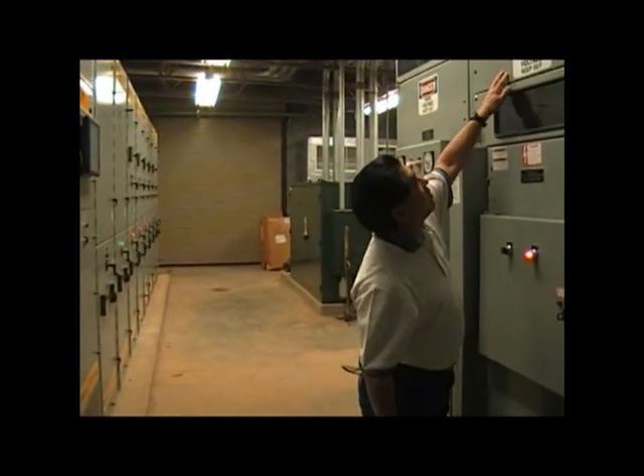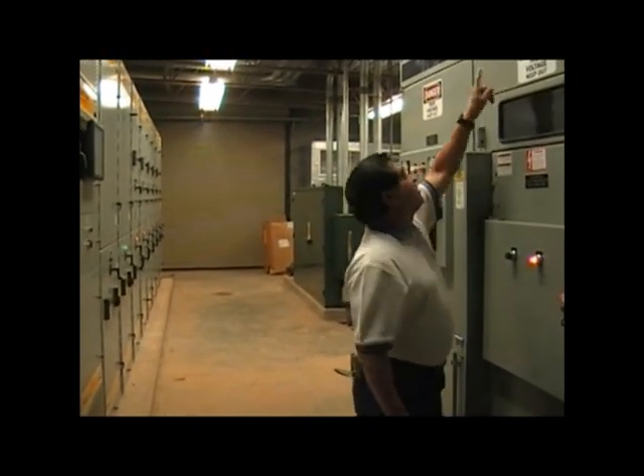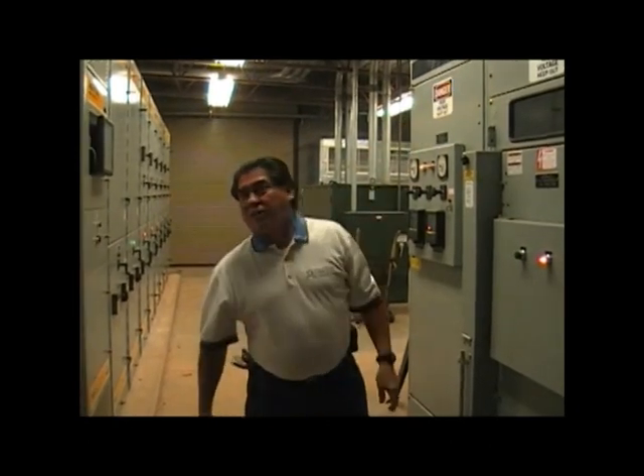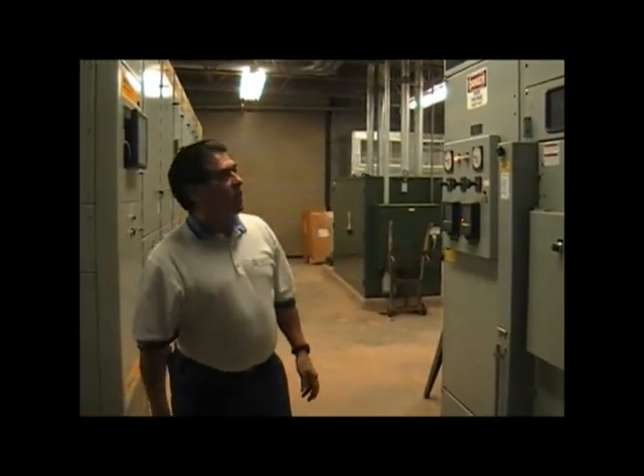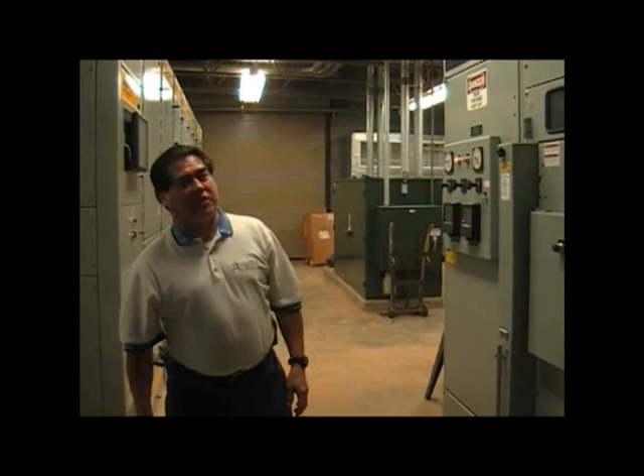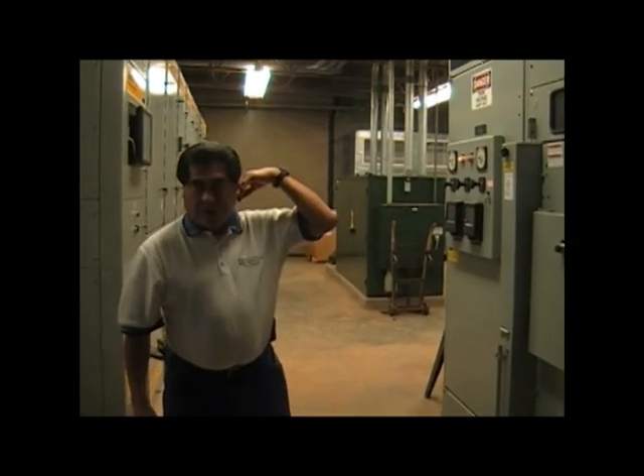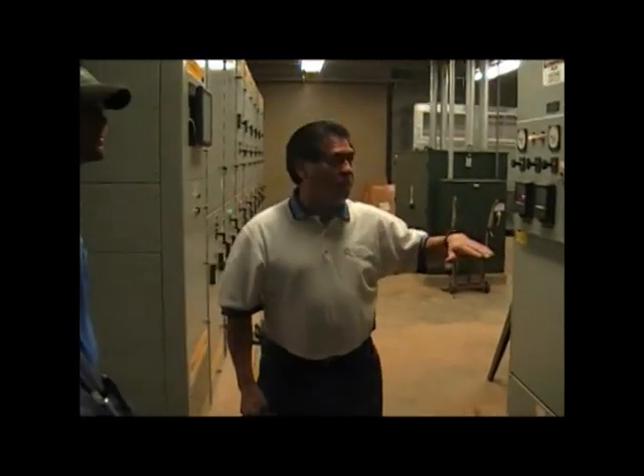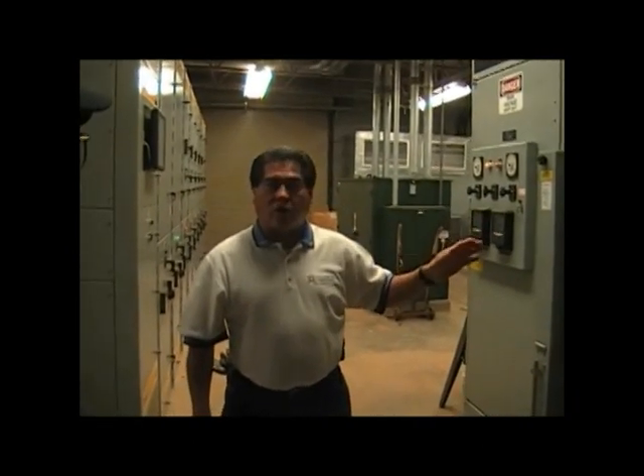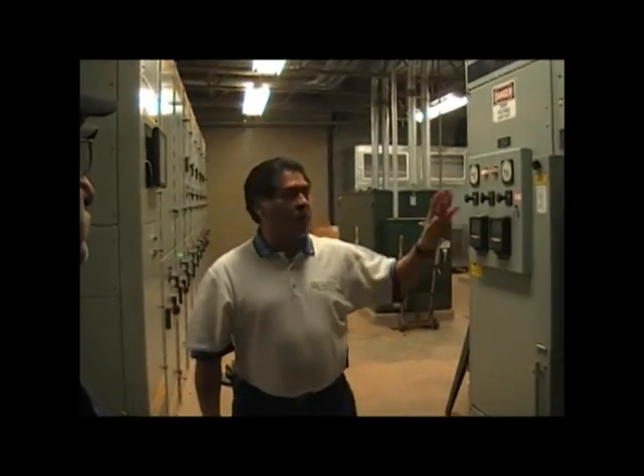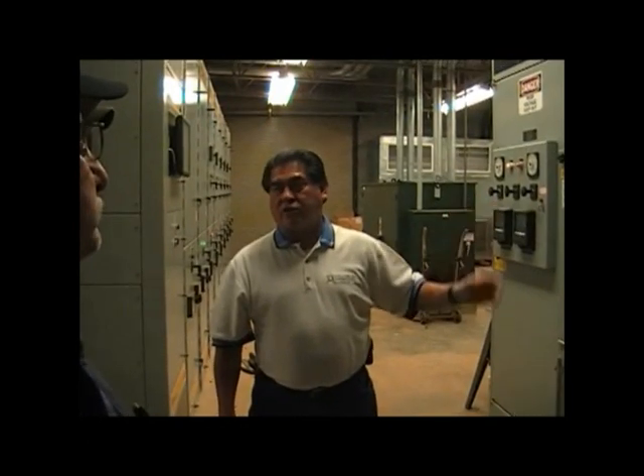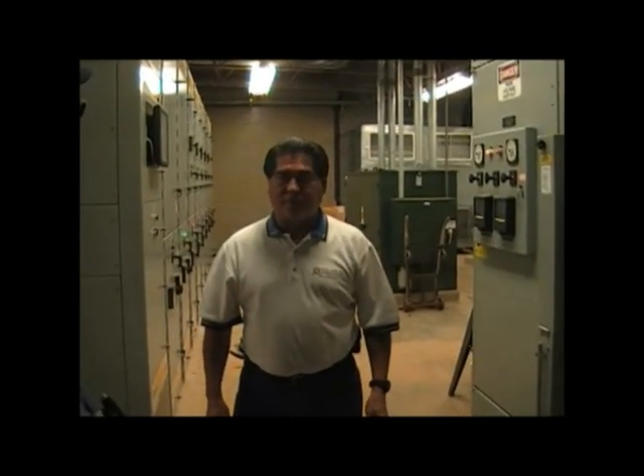Looks like they've done some external maintenance, trying to clean it up a little bit - you can see they've done some wiping there. You've got to be careful that they don't spray stuff that gets onto the current carrying conductors, because any kind of liquid or moisture on current carrying conductors is going to cause some type of erosion.